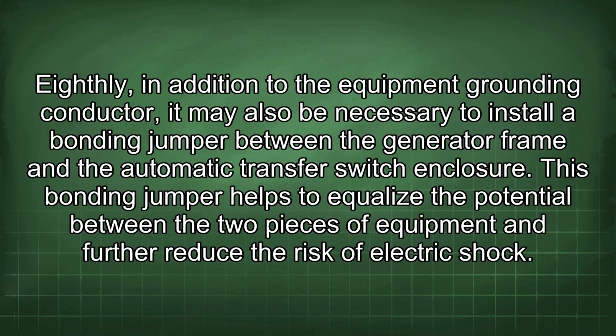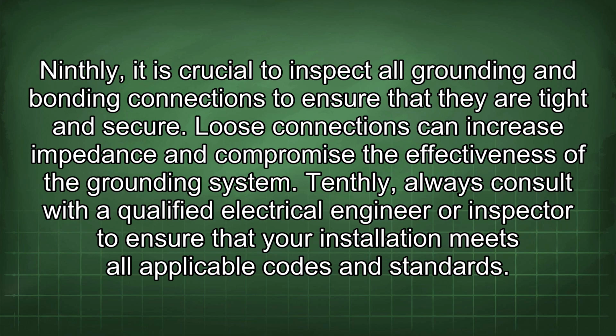Eighthly, in addition to the equipment grounding conductor, it may also be necessary to install a bonding jumper between the generator frame and the automatic transfer switch enclosure. This bonding jumper helps to equalize the potential between the 2 pieces of equipment and further reduce the risk of electric shock. Ninthly, it is crucial to inspect all grounding and bonding connections to ensure that they are tight and secure. Loose connections can increase impedance and compromise the effectiveness of the grounding system.